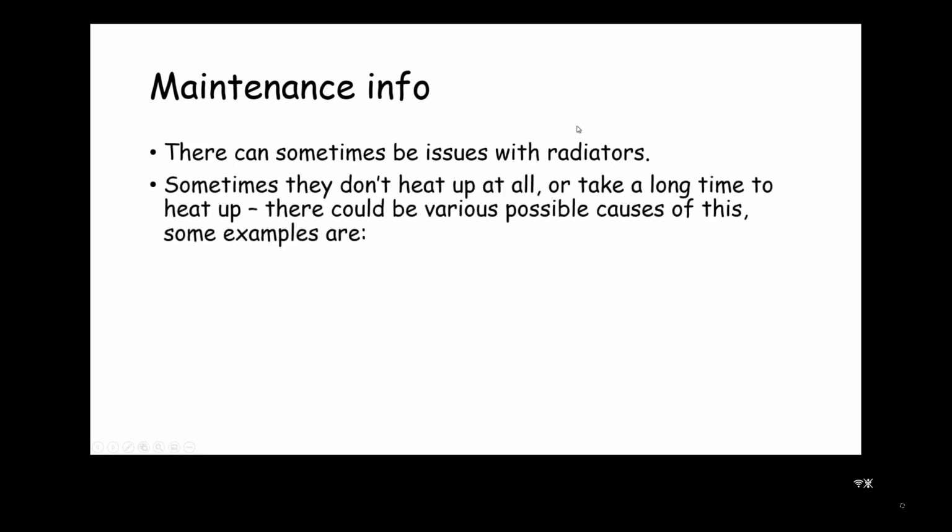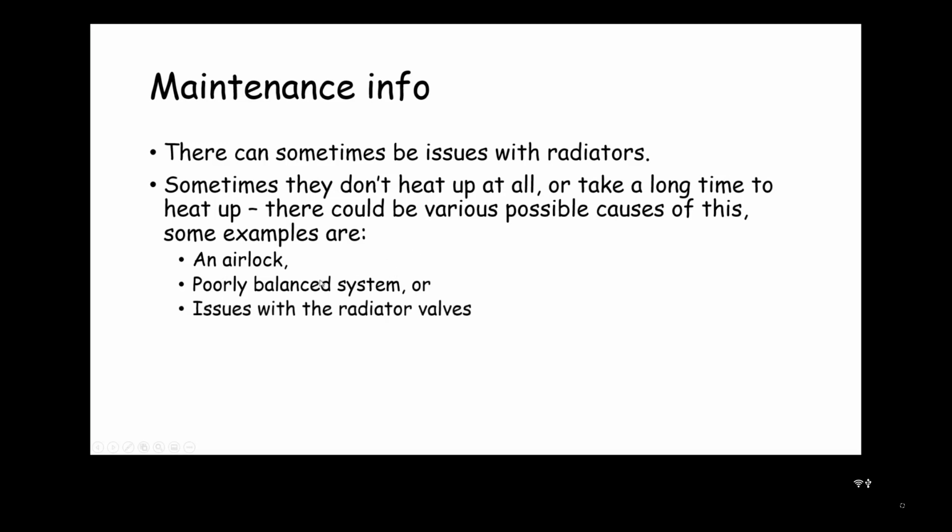There can obviously be issues with radiators, as there can with any part of the system potentially. The main issue is to do with them heating up or not heating up, or partly heating up essentially. And there's different causes for these. One could be a complete airlock. If it doesn't heat up at all, it might be completely full of air, or there might be an airlock in the pipework. It could also be a result of a poorly balanced system. It could also be potentially an issue with radiator valves. Or if the whole system isn't heating up, then it could be an issue with the boiler or pump. But if it's individual radiators, these are the most likely causes.